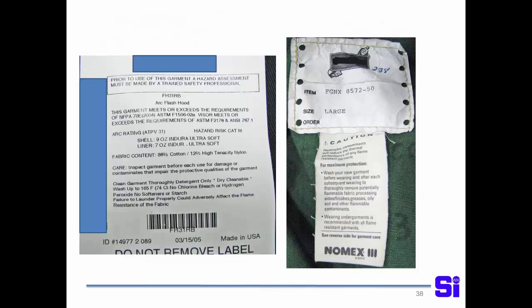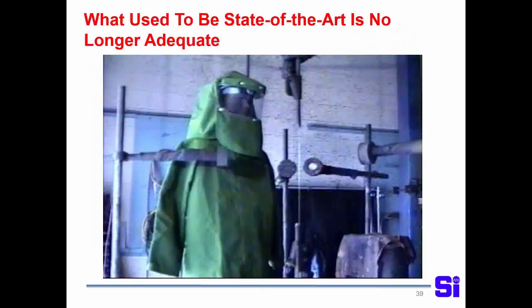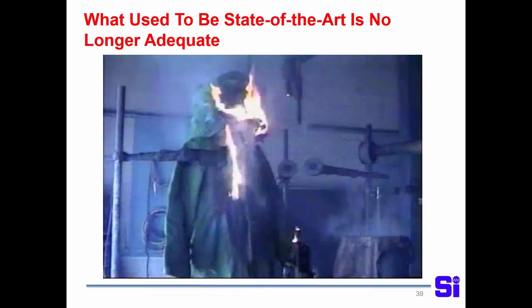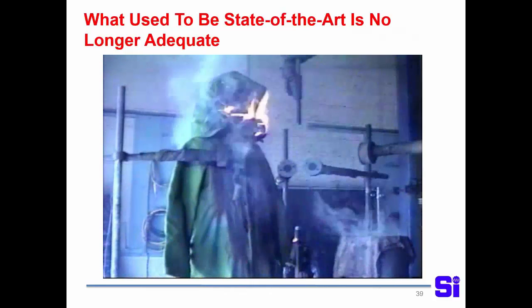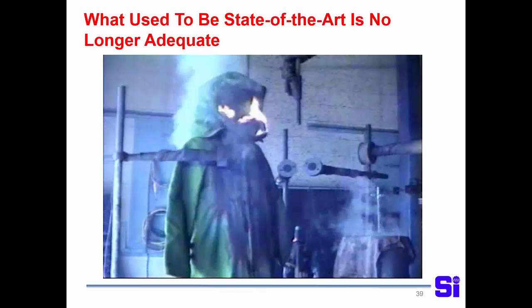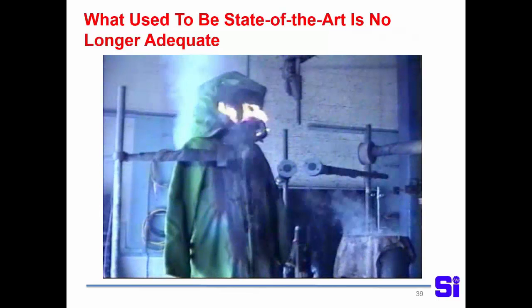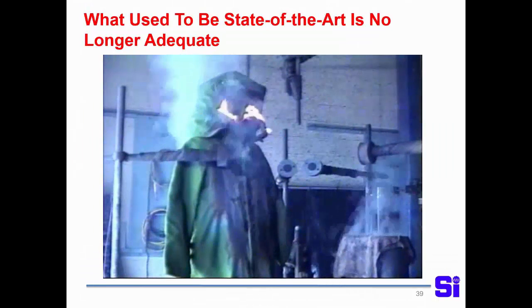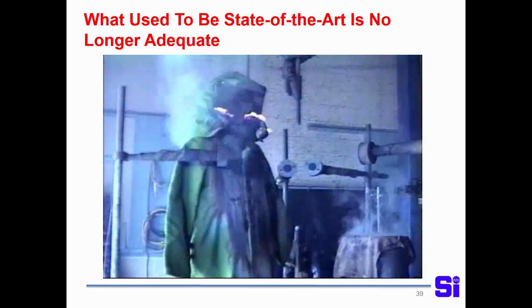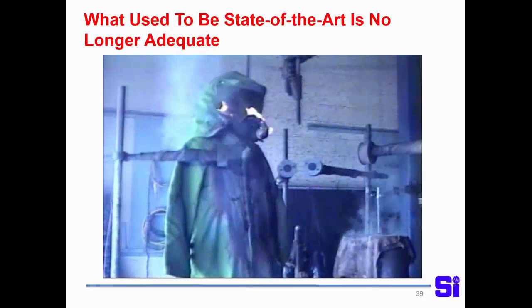But it tells you that it's in compliance with the appropriate standard. Here's a video that I have of arc testing of that same type of arc flash suit. And you can see that the chest of the arc flash suit held up pretty good, but that polycarbonate window melted and collapsed onto the mannequin's face.